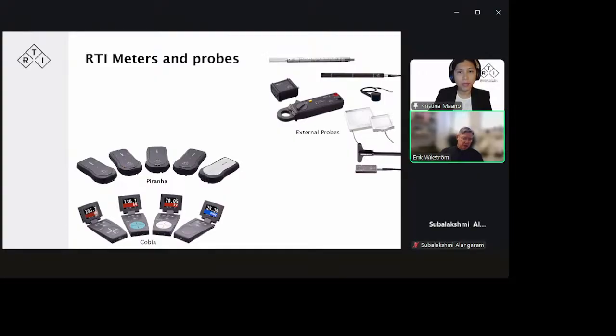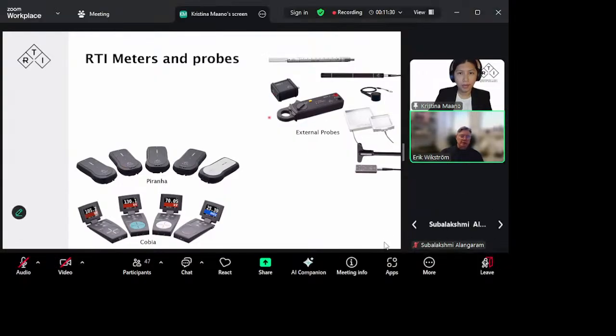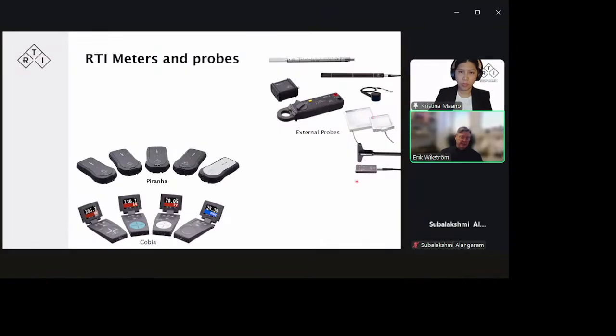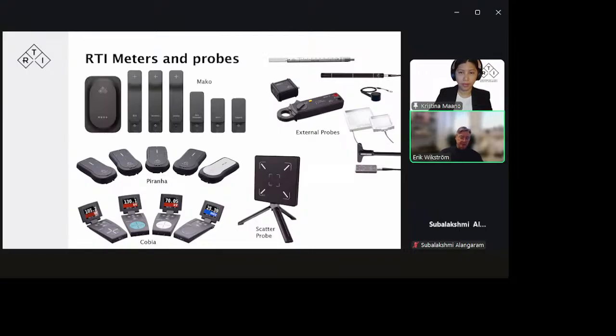To handle other applications or other measurements, there's a bunch of external probes to be able to measure CTDI, for instance, beam width, mA, mAs. We have chambers that help us measure DAP, dose area product, or CAP, etc. So to make the selection more complete, we also have a scatter probe, which we'll be focusing on today, to be able to measure scatter and leakage. So it's the leakage and the secondary radiation in an X-ray application. That's what we're focusing on today.